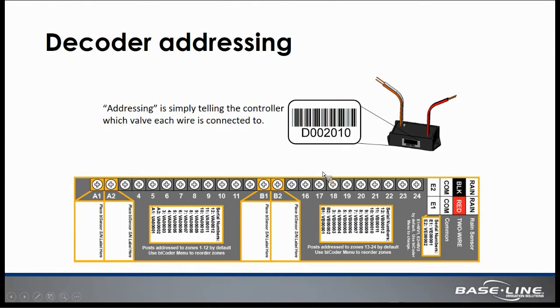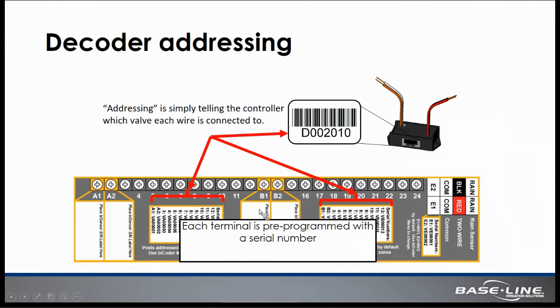So when we're dealing with a retrofit situation with conventional wire, like an in-field 2-wire decoder that has a unique serial number associated with it, each one of the posts that the conventional wire is connected to also has a unique serial number associated with it, and those serial numbers are used in the configuration in the program controller. So again, it gives us the ability to configure a site and program a pre-existing site that was conventional wire with 2-wire methodologies and performance capabilities.